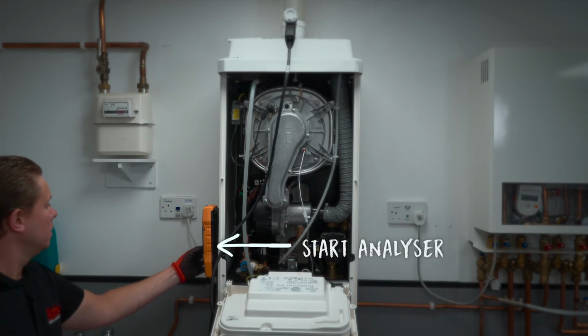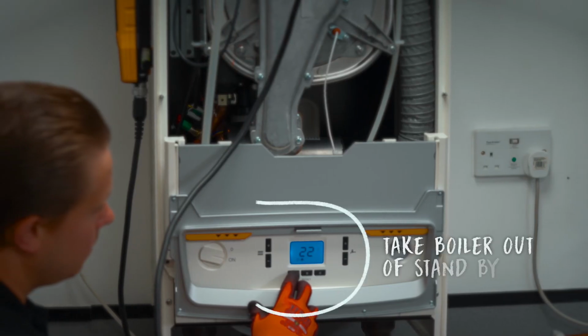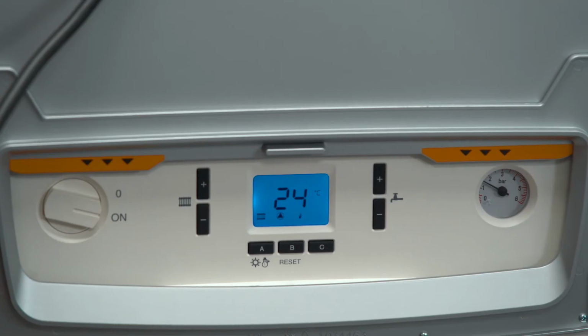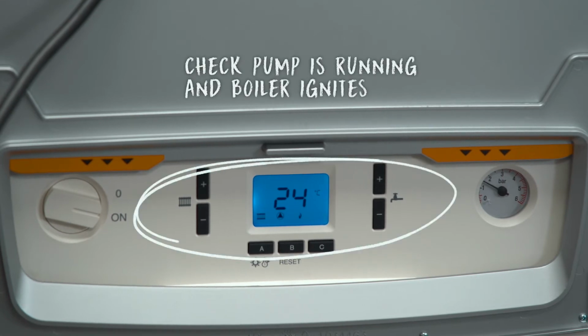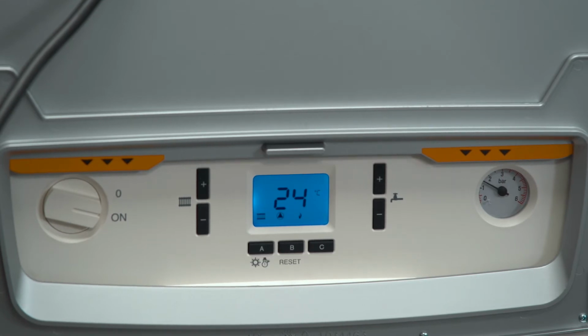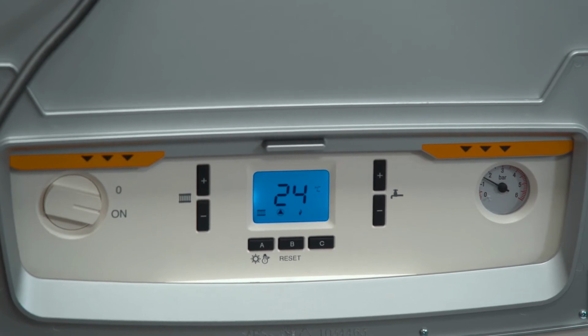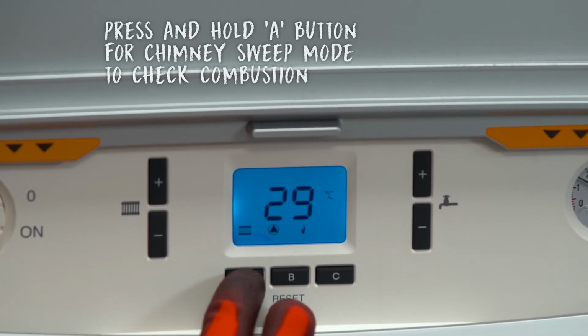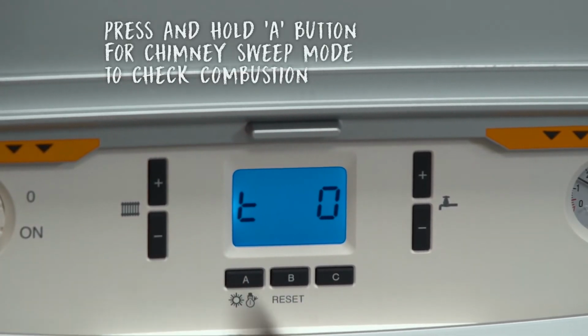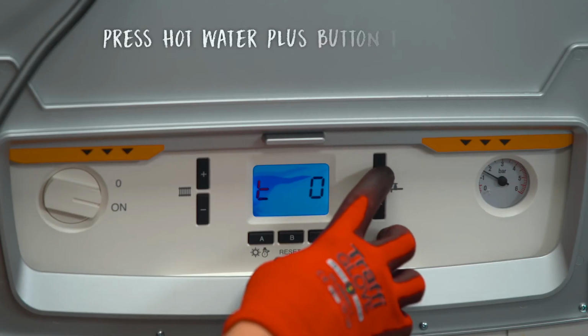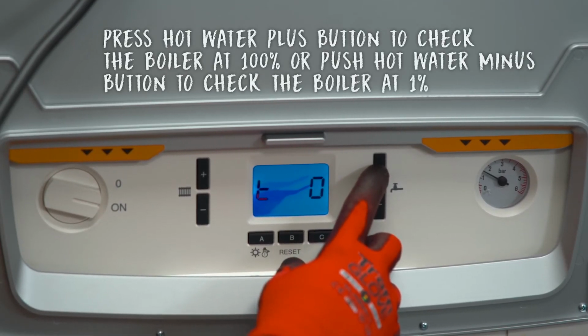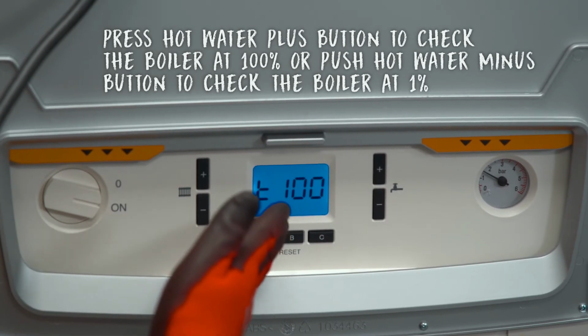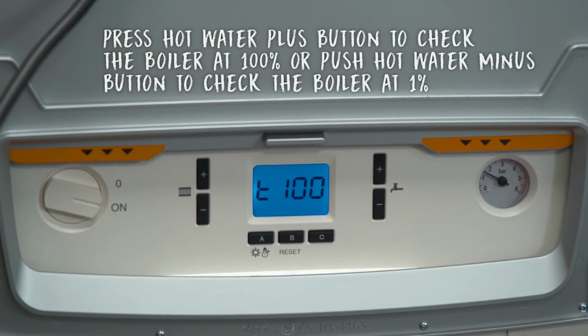Start the flue gas analyzer. Next, take the boiler out of standby by pressing the A button once. Check for radiator, pump and flame symbols to confirm the boiler has ignited. Press and hold the A button to engage the chimney sweep mode to check combustion. Then press the hot water plus button to check the boiler at 100%, or push the hot water minus button to check the boiler at 1%.